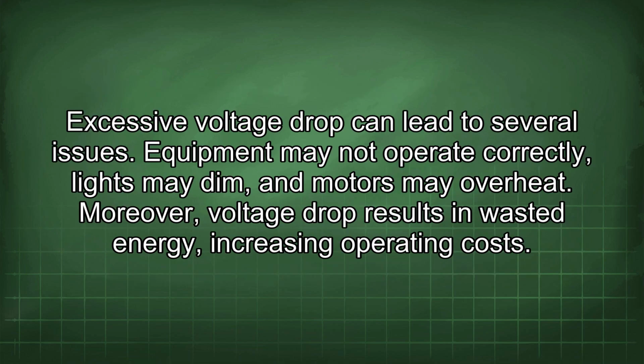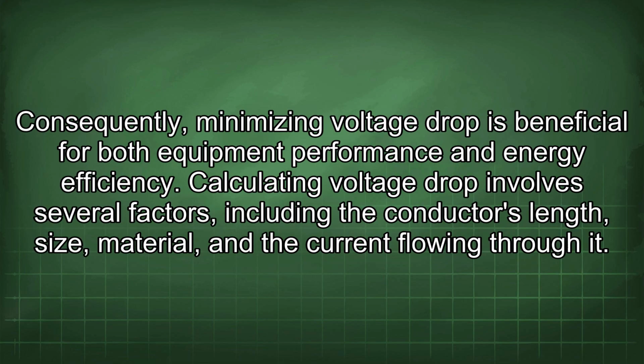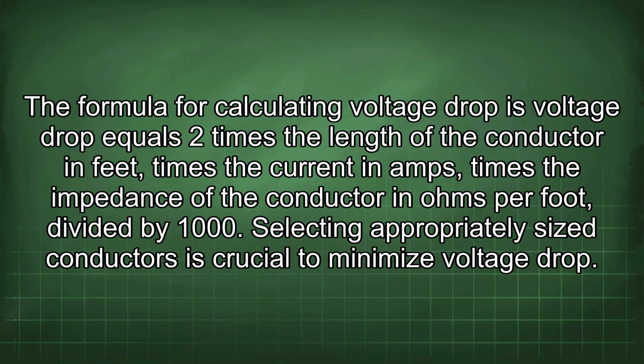Excessive voltage drop can lead to several issues. Equipment may not operate correctly, lights may dim, and motors may overheat. Moreover, voltage drop results in wasted energy, increasing operating costs. Consequently, minimizing voltage drop is beneficial for both equipment performance and energy efficiency. Calculating voltage drop involves several factors, including the conductor's length, size, material, and the current flowing through it. The formula for calculating voltage drop is voltage drop equals 2 times the length of the conductor in feet times the current in amps times the impedance of the conductor in ohms per foot divided by 1000.